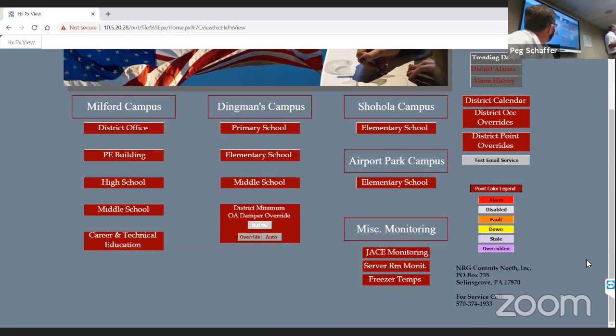Before I wrap up, some of the things you have the ability to use in the system, the maintenance folks can do. There's a district outside air damper override. We can hit that button and every damper we're connected to can open to whatever percentage they put in. So if they say, I want to purge that building, let a lot of fresh air in, they can override the dampers for a period of time and then shut it off, or put it on a timer, to allow fresh air at different times as needed.